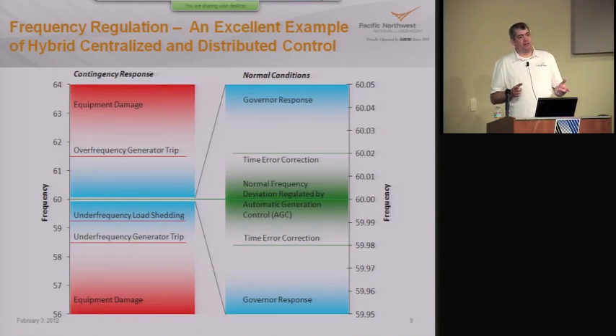So now let's think about this for a second. If our frequency is high, say at 62 hertz, and my generation needs to start tripping to protect itself, that's going to be naturally a self-correcting thing, because if frequency is high, what that means is my supply was greater than my demand. That's why the frequency was high. And so if I'm tripping generators, that's going to be a self-correcting phenomenon, and it will bring me back towards nominal, just naturally. But if my frequency is low and I trip due to underspeed, that's a serious situation. If I ever trip a generator due to underspeed, I'm already generation deficient, and if I then trip a generator, it's just going to make the problem worse. And that's when you have a cascading failure and leads to a blackout within that region.